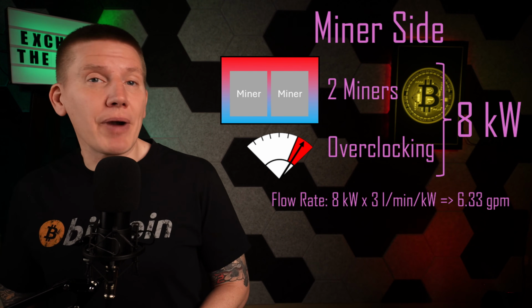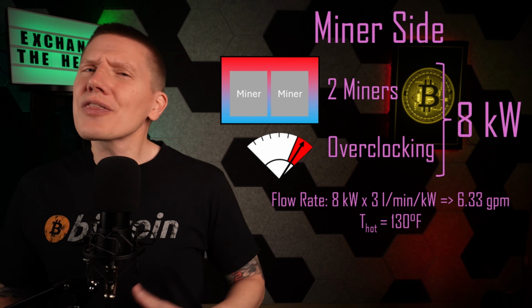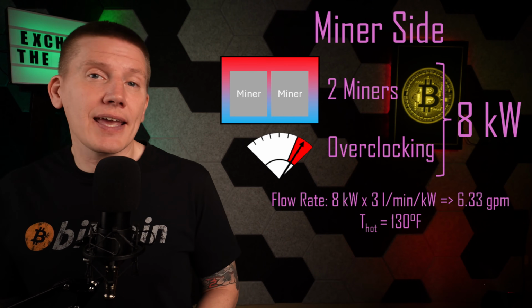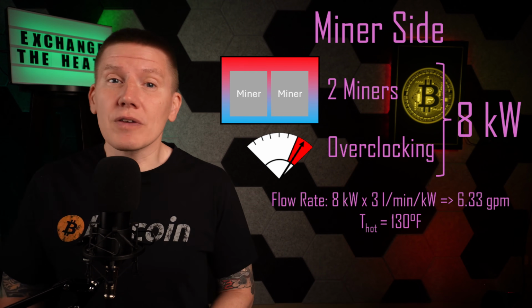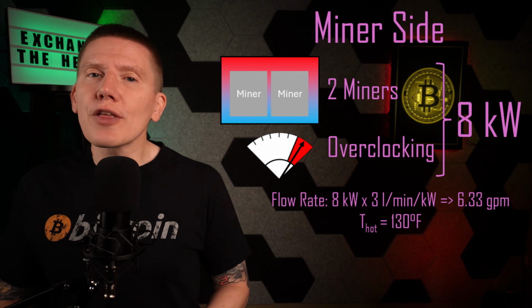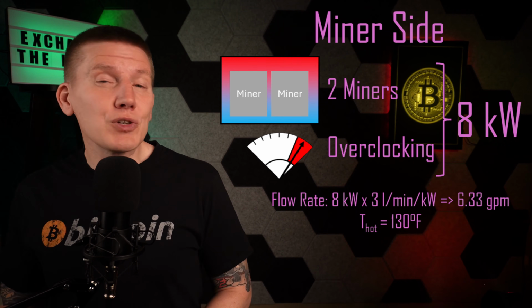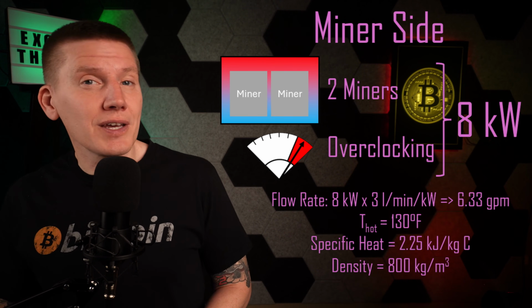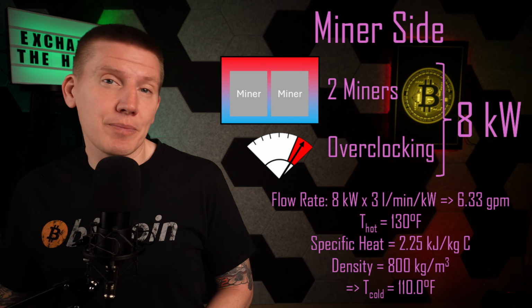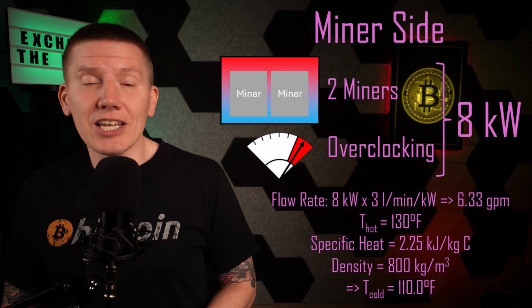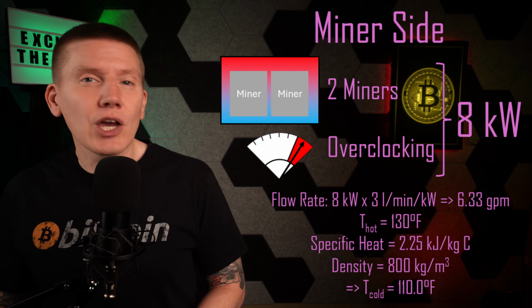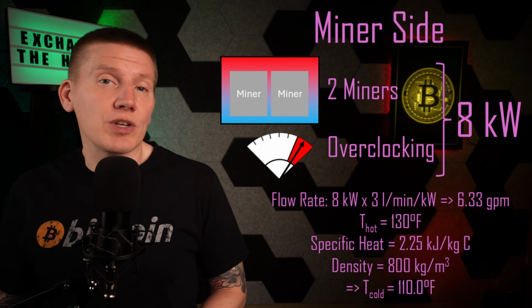And to protect my miners from overheating, I'll set the maximum output temperature of the tank, which is the input temperature of the heat exchanger, to 130 degrees Fahrenheit. If I'm using a typical dielectric fluid, the math shows the output temperature of the fluid exiting the heat exchanger and re-entering the tank will be about 110 degrees Fahrenheit.